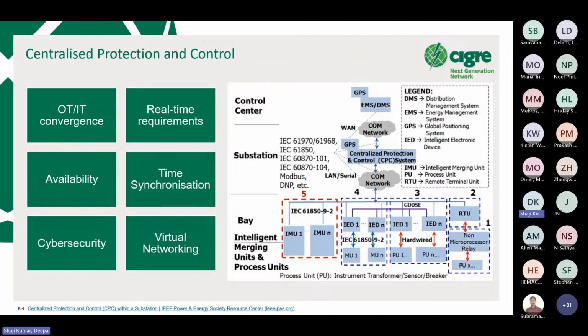The core principle behind the centralized protection and control approach is to consolidate the protection and control features from several bay level units onto one central processor located in a substation. This would leave only process interface tasks to merging units at bay level.